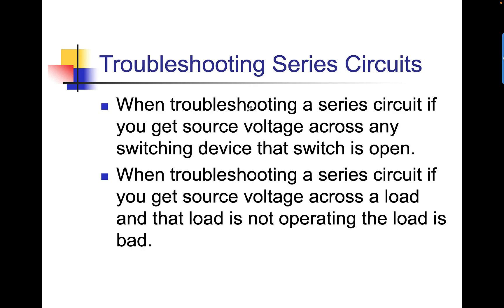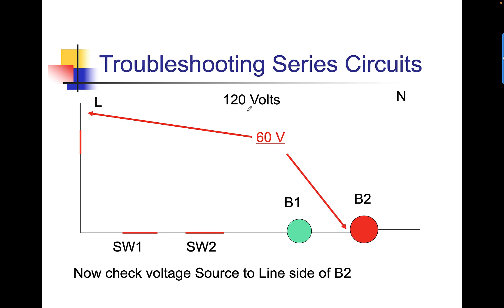When troubleshooting a series circuit, if you get source voltage across a load and that load is not operating, the load is bad. So if we go back here and if I get source voltage across B1, but B1 is not operational, it tells me there's an open in B1 and that load is bad.